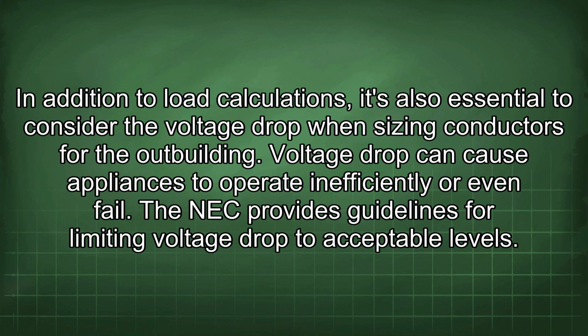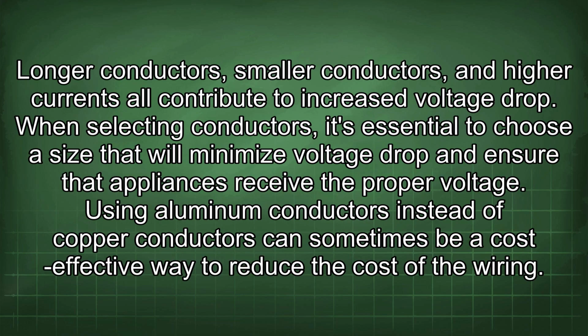In addition to load calculations, it's also essential to consider the voltage drop when sizing conductors for the outbuilding. Voltage drop can cause appliances to operate inefficiently or even fail. The NEC provides guidelines for limiting voltage drop to acceptable levels. Longer conductors, smaller conductors, and higher currents all contribute to increased voltage drop. When selecting conductors, it's essential to choose a size that will minimize voltage drop and ensure that appliances receive the proper voltage.